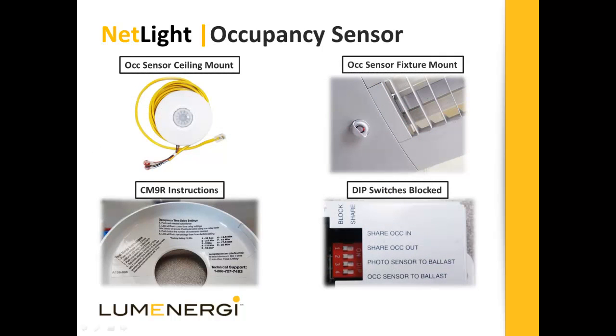Occupancy sensors may be ceiling or fixture mounted. The ceiling plan may not display the best physical location of the sensor. A sensor comes programmed with a default time delay. Ensure you reset this to the minimum time by following the instructions of the sensor. All dip switches should be set to block.